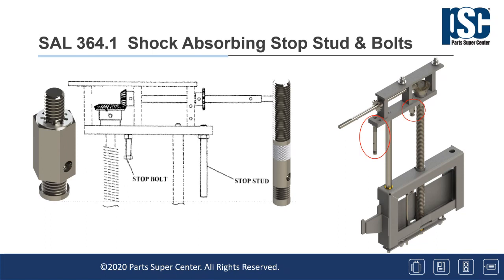The shock absorbing stop studs and bolts were designed after recognizing that either on purpose or through misadjustment of the upper limit switch, the stop studs were being used to stop the breaker when it is being elevated into the connected position. Again, this can create excessive wear on the clutch assembly, the elevating gears, and the motor when the unit elevating system comes to an abrupt stop.